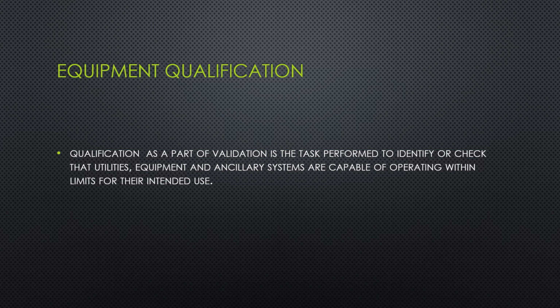qualification is performed to check that all the utilities, all the equipment, all the ancillary items that are being used in the manufacturing of the product are within the limits, and those results are within the intended purpose and within the acceptance criteria. So based on those acceptance criteria limits, the equipment is used in the manufacturing of the product. Based upon the qualification and all the results, the qualified equipment is used in the validation of the product. As the equipment will have an impact upon the quality of the product as well as the yield of the product, that is the reason why equipment qualification plays a major role in the validation.